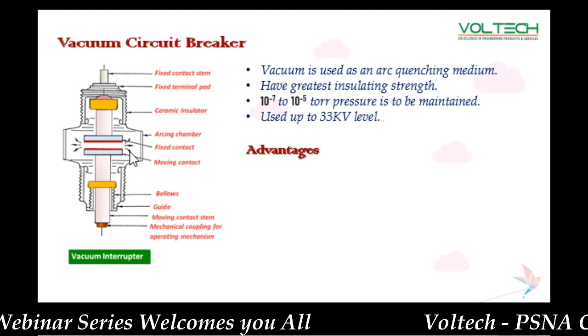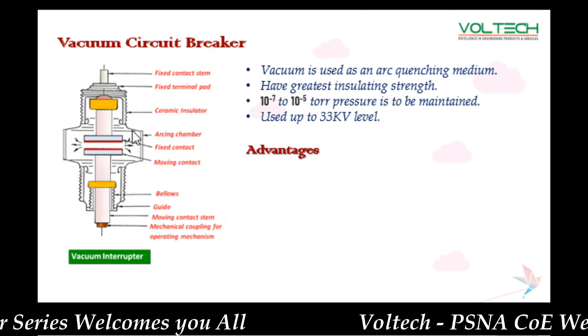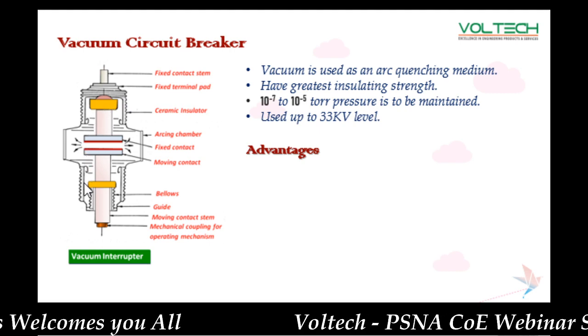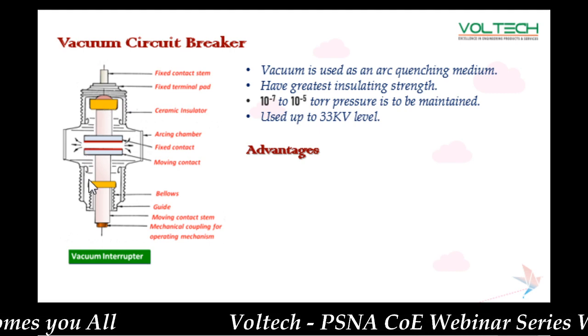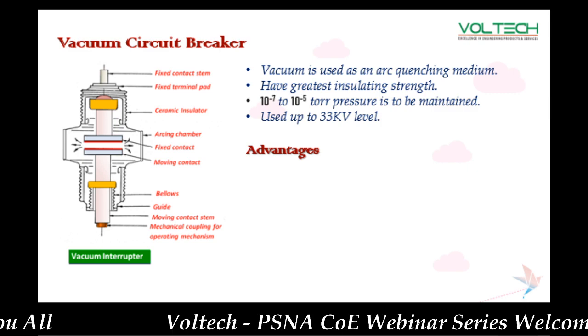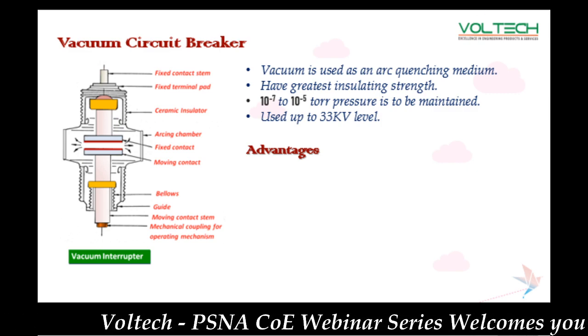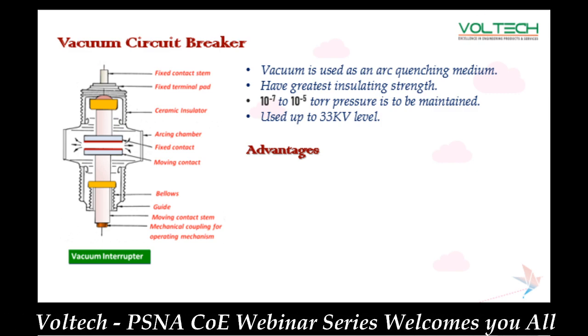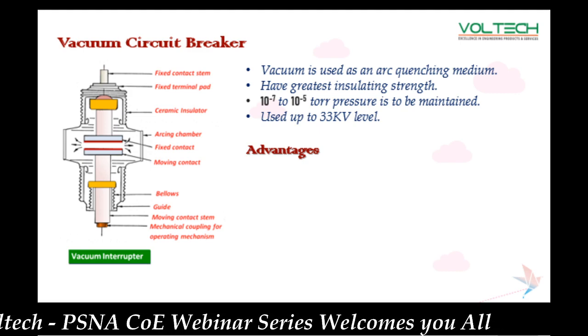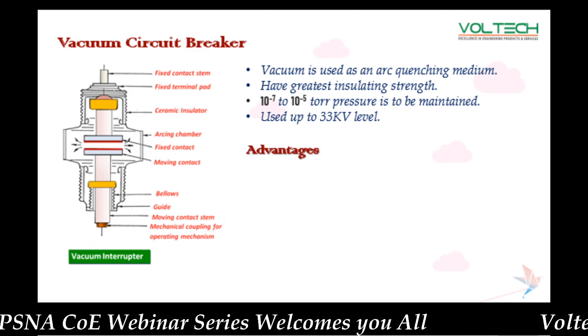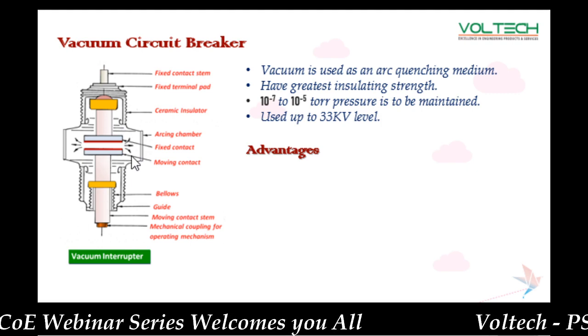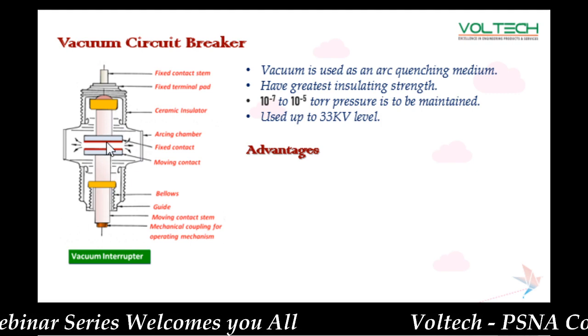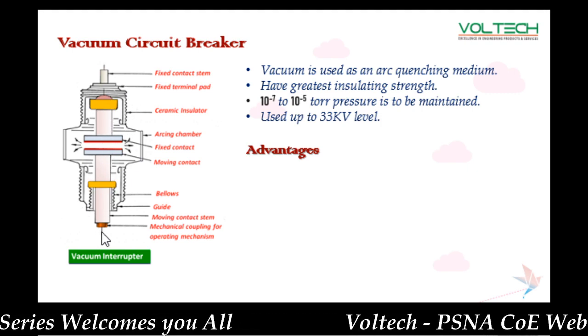So this is the vacuum interrupter. This place is filled with vacuum. We fill it with vacuum because if there is no air, there is no chance of an arc. Here the vacuum pressure is about 10^-5 to 10^-7 torr, and this vacuum breaker is used up to 33 kV. Here this contact is fixed and this one is moving.